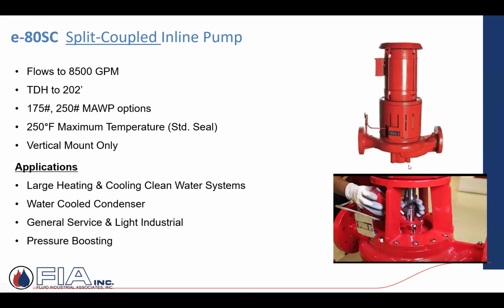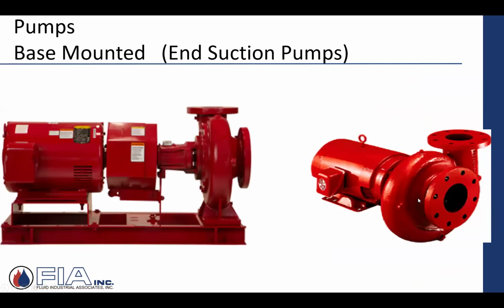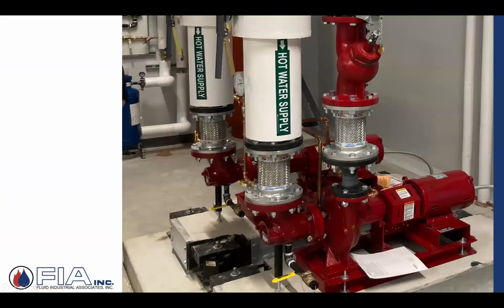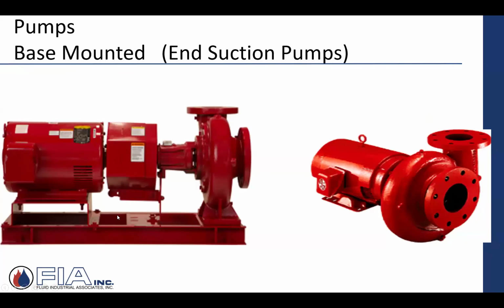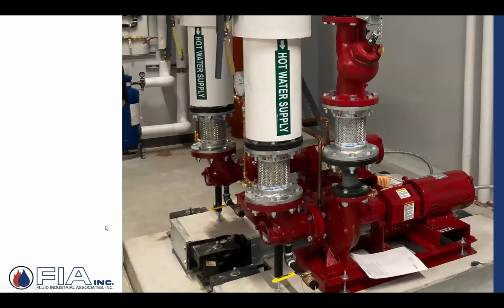And it's why they're probably going to offer some type of base support to support it. But they're showing kind of a cutaway of that split coupled where the technician can get access without touching the motor that's up above it to get to that impeller, get to that seal, etc. End suction, just like we talked about, these two pumps are both end suction. One's a close coupled with a little foot base right here. And then obviously the one on the left here is with a coupling, with a bearing assembly, coupler guard and a motor sitting on a frame, sitting on a base. Both are what you refer to as that end suction.